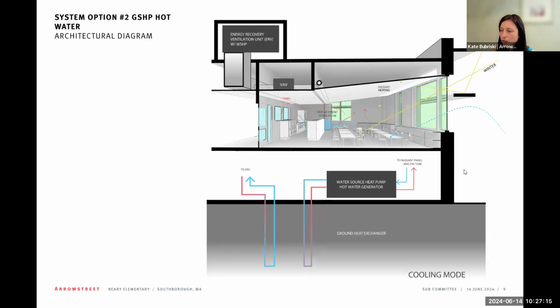Option 2 is going to look very similar, except you won't see the radiant cooling panels at the perimeter. You will have some supplemental radiant heating at the perimeter, but the ventilation system, regardless of what type it is, is doing the bulk of your cooling and dehumidification for the space, because you don't have chilled water, you won't have the radiant cooling.